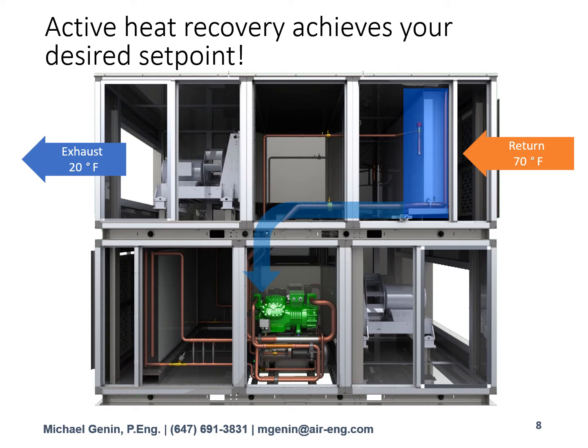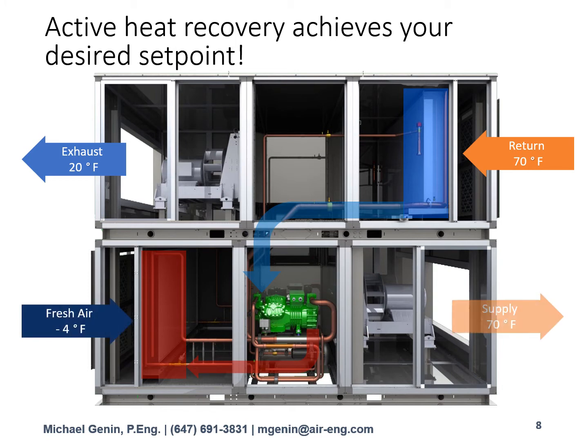Then the compressor compresses this and discharges it to the condenser coil or the heating coil. And then this allows us to bring our outside air stream across that condenser and heat it up to the desired supply temperature. So in this example, the fresh air unit is able to heat the supply air to our desired 70 Fahrenheit with a return air that's also at 70 Fahrenheit with no top-up energy required.